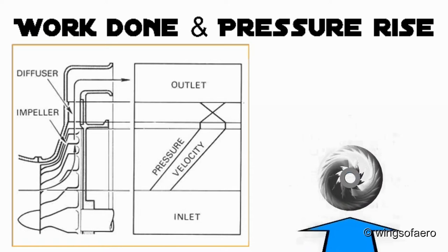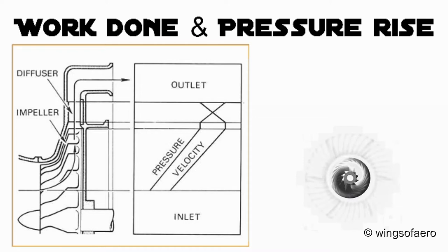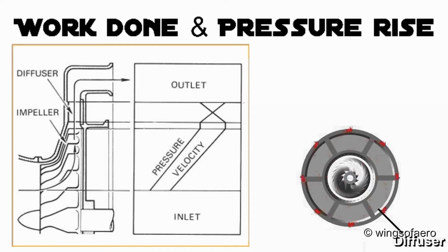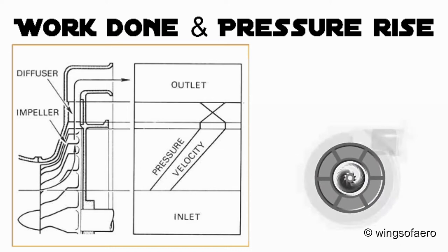To convert the kinetic energy of the fluid at the impeller outlet gradually into pressure energy, diffuser blades mounted on a diffuser ring are used. The stationary blade passages are formed with an increasing cross-sectional area, which reduces the flow velocity and hence increases the static pressure of the fluid.